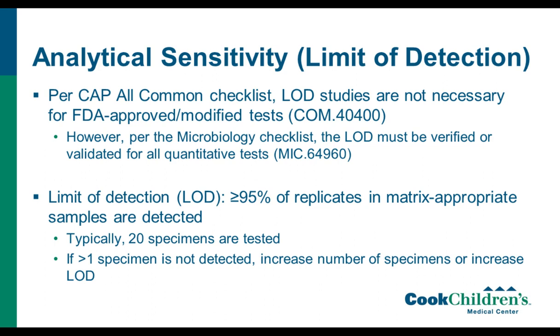And so limit of detection studies, the limit of detection is defined as greater than or equal to 95% of replicates are detected. So typically 20 specimens are used, and as long as 19 of these are detected, you can say that that is the limit of detection. However, if you run 20 samples and more than one isn't detected, you'll have to increase your number or increase your LOD. Some people will do less if they're running an FDA-approved test. If they're staying on label, they may just run a few replicates to verify the manufacturer's limit of detection and do a more extensive limit of detection study if it's off-label or an LDT.